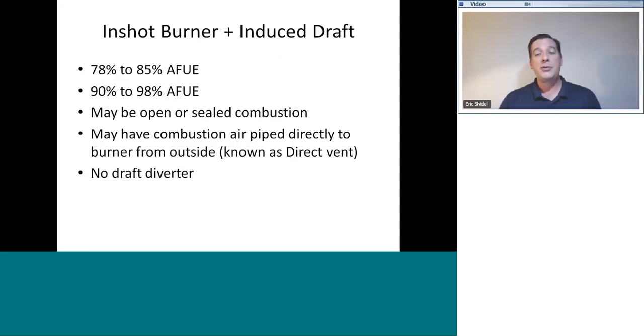So inshot burners with induced draft appliances can be either 78 to 85% AFUE, we would call that a mid-efficiency appliance, or they can be 90 to 98% AFUE, which would be a high-efficiency appliance. They may be either open combustion or sealed combustion. Sealed combustion simply means that the burners are sealed, you can't just reach in and touch them, and often there will be a dedicated combustion air pipe going directly from the burners to the outdoors to draw in fresh, clean combustion air. And that can be present on a 90% furnace or an 80% furnace.